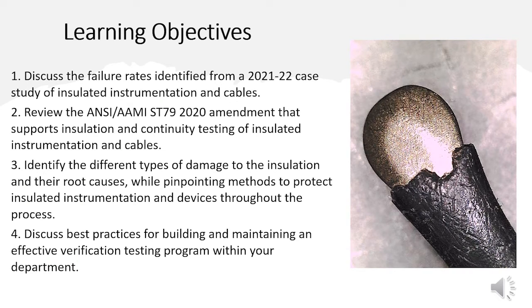The objectives: we're going to look at failure rates identified in a 2021 to 2022 case study of insulated instrumentation and cables. We're also going to review the ANSI AAMI ST79 2020 amendments that support insulation and continuity testing. We're going to identify the different types of damage to the insulation and the root causes, while pinpointing methods to protect insulated instrumentation and devices throughout the whole process. We're also going to be looking at best practices for building and maintaining an effective verification testing program within your department.